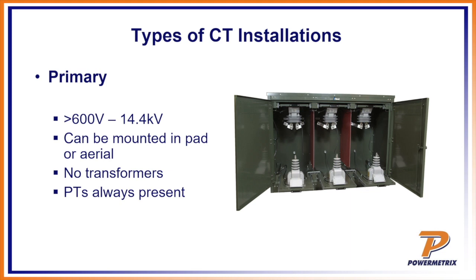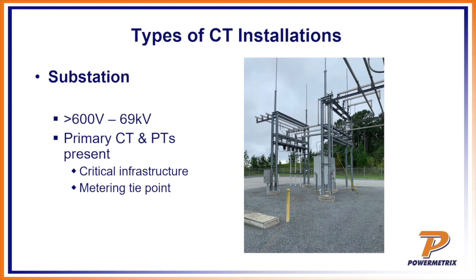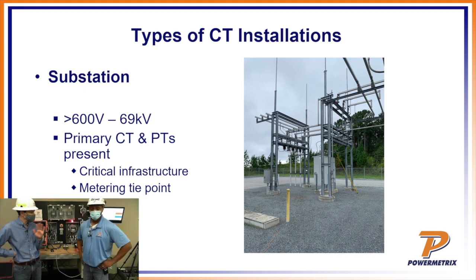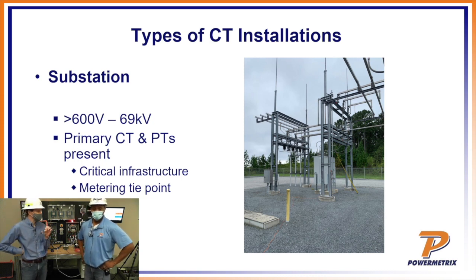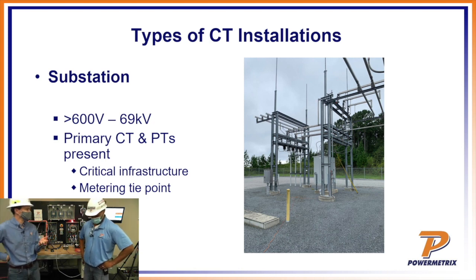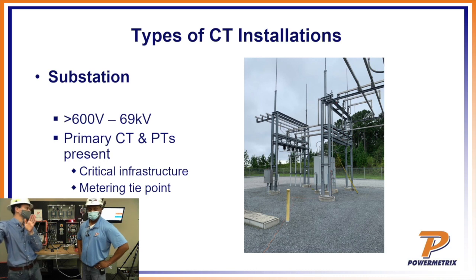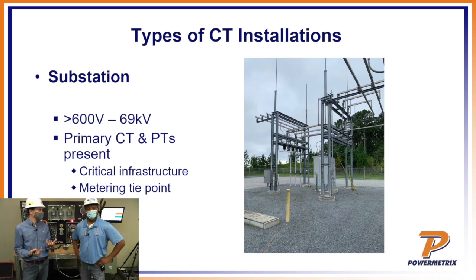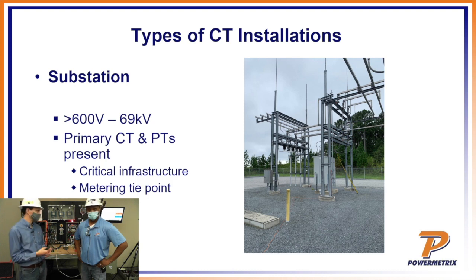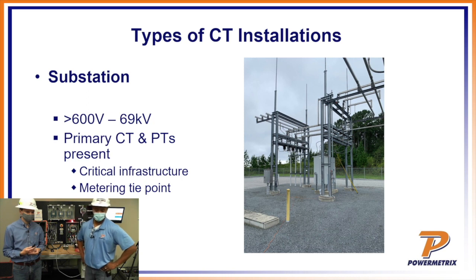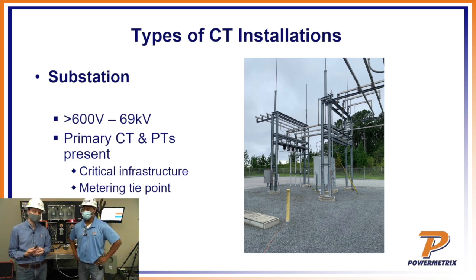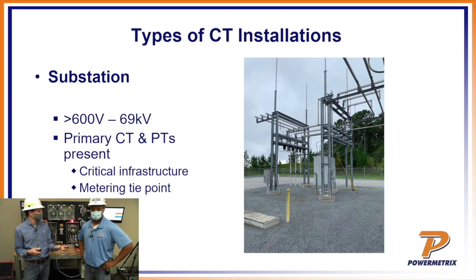The last installation type is a substation application. These are always primary, and you'll typically see up to 69kV on distribution-side substations. CTs and PTs are always present. This is a critical billing point — the transfer point between generation and distribution — so it's absolutely essential that the CTs and meter are correct, because a problem here can be a huge billing issue. Figuring out where to place your probe at a substation can be complicated, and we have a great customer example of that later in the presentation.